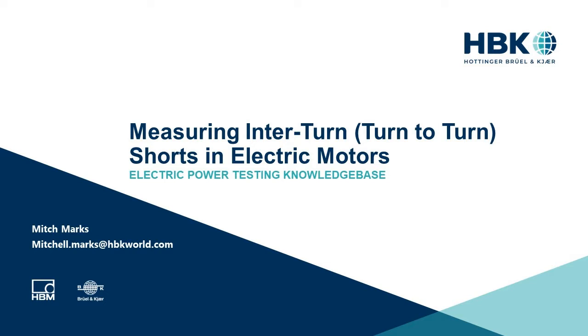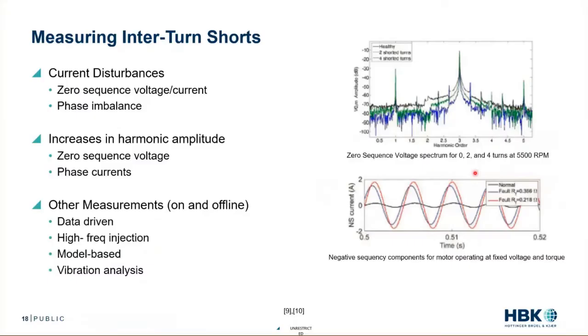It's happening — inter-turn shorts. These are, again, the two windings in the stator getting shorted together. So when you short two windings together, you get big currents. Big currents mean there's stuff we can measure.